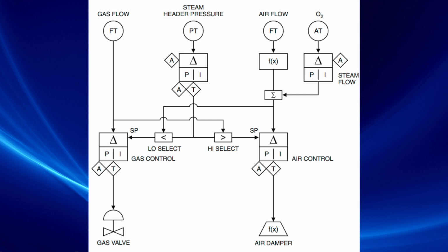The advantage of this system is that on a load increase, fuel demand cannot be increased until an actual increase in airflow is measured. On a load decrease, air demand cannot be decreased until an actual decrease in fuel flow is measured. On an inadvertent decrease in measured airflow, the fuel demand is immediately reduced in equal amount.